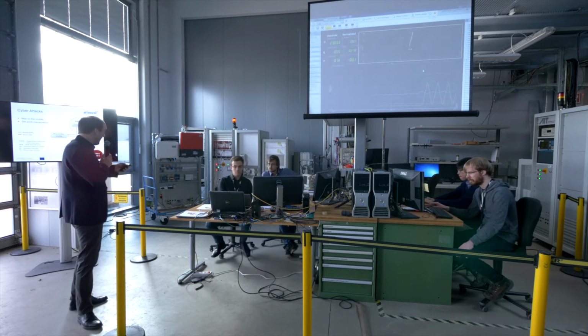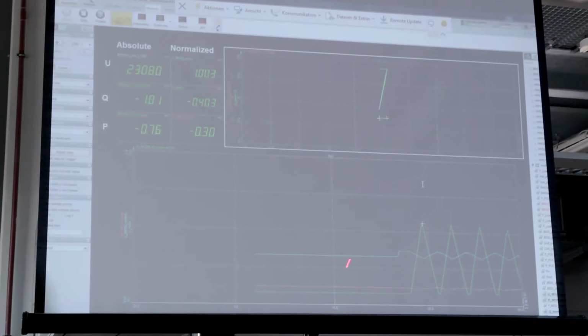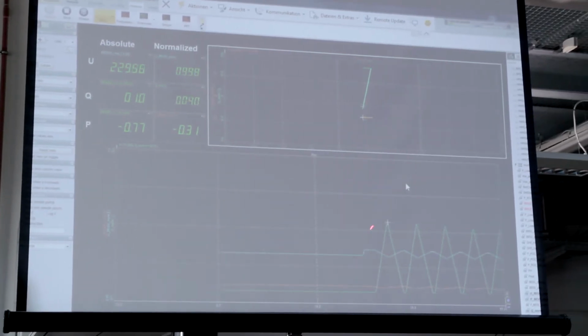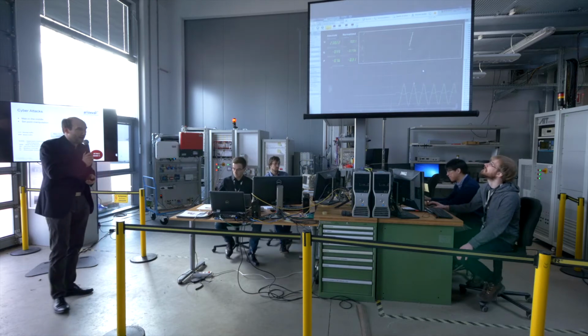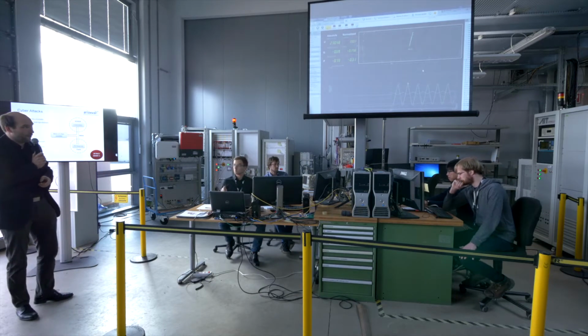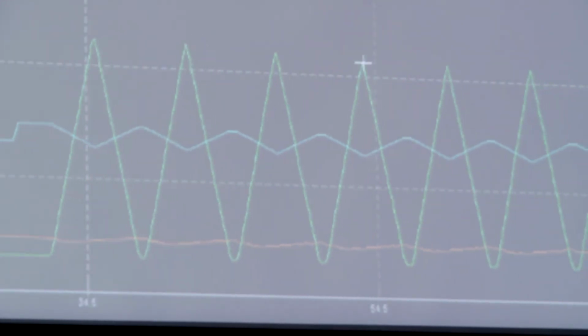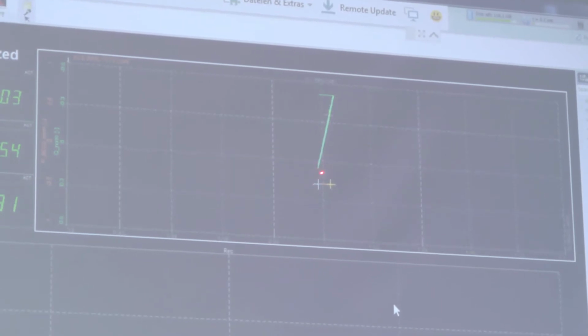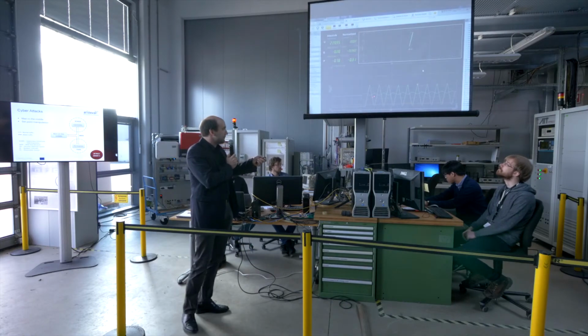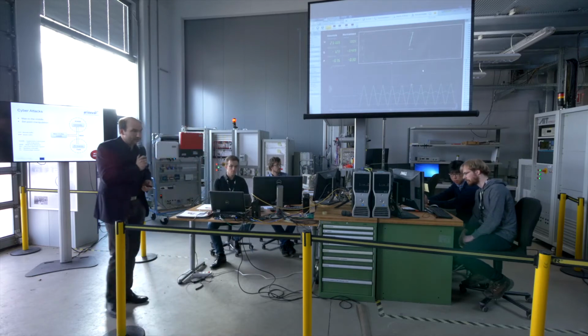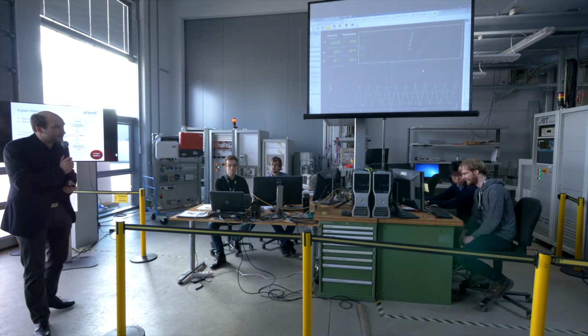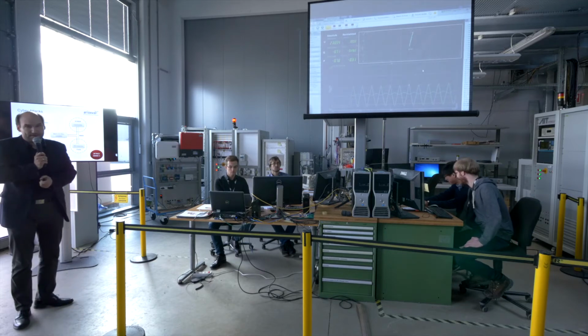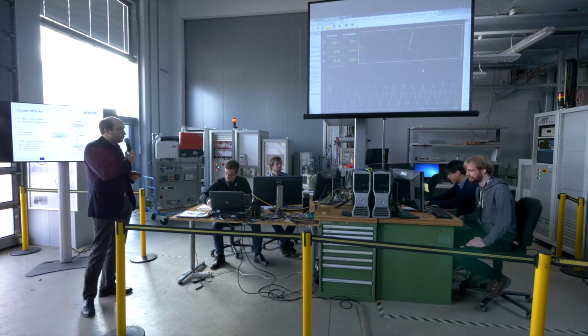And there we are - the attack has happened, and the result is quite disastrous. You see here, green is the reactive power and blue is the voltage. Reactive power is swinging around, oscillating now, because we have this very high gain in the curve. You can also see on the top chart, this is basically voltage against reactive power, so the current system state is always oscillating between these two points on the curve. We have a very significant impact on the voltage on the system - this oscillation would actually be visible in light bulbs, and could also destroy sensitive equipment like efficient light bulbs or motor drives in the system.